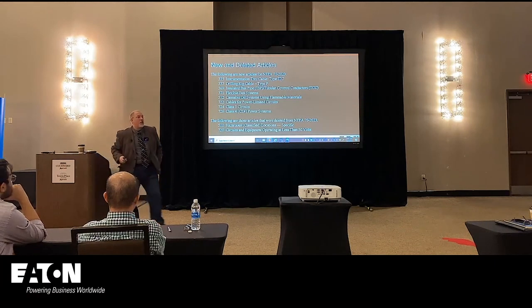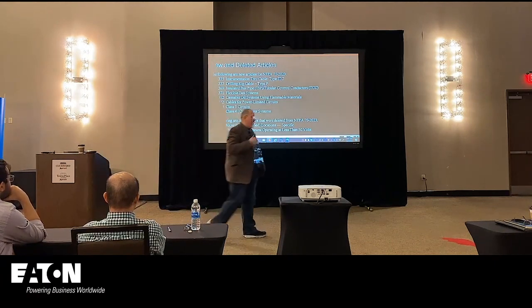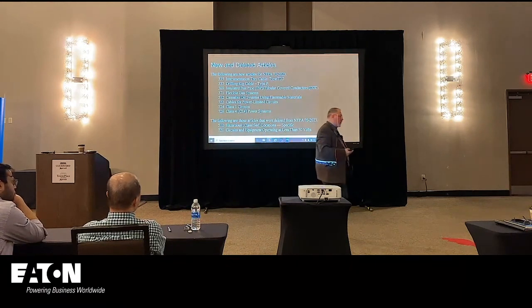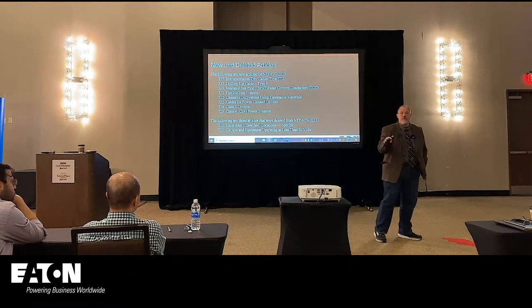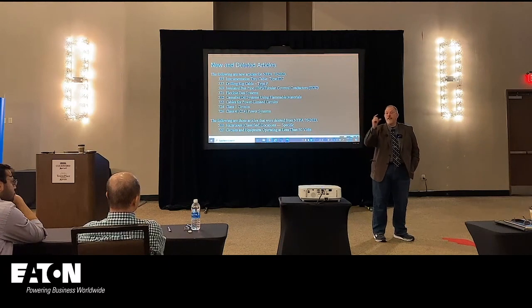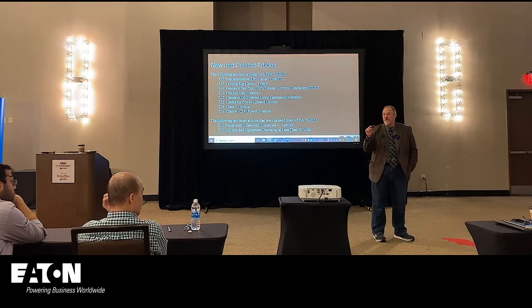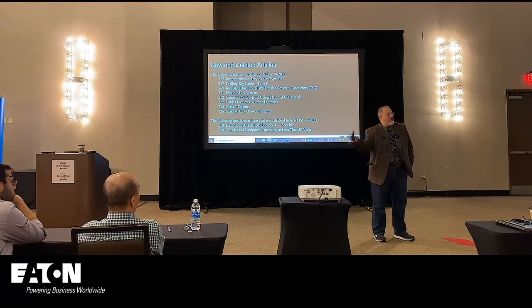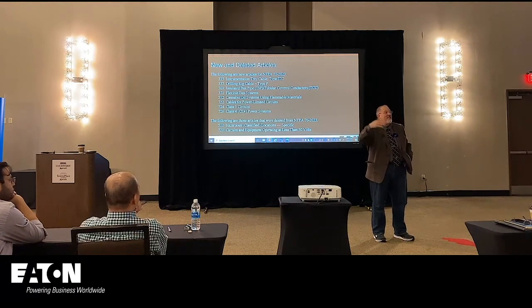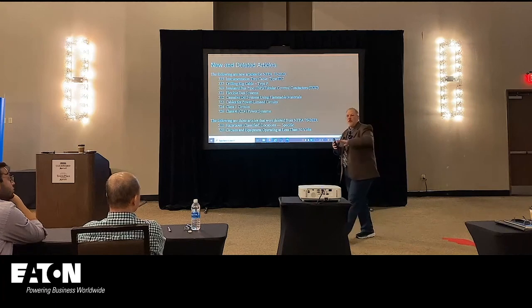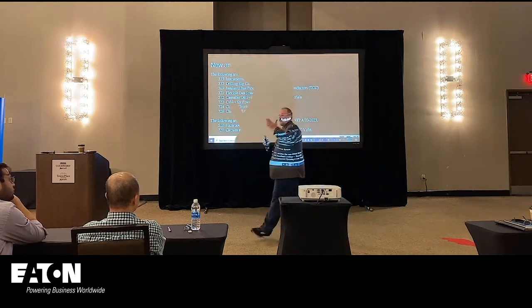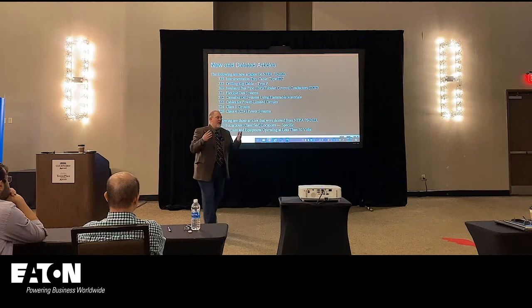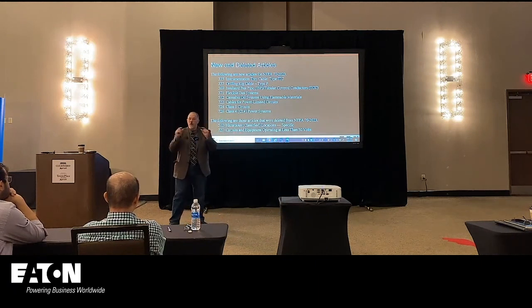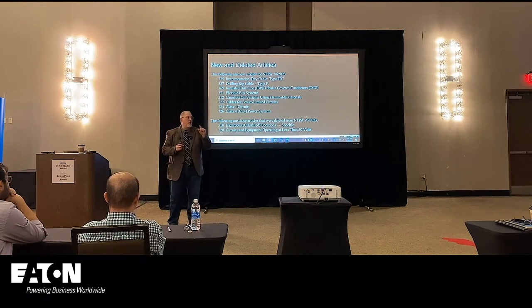Power limited in Class 4, there's a new technology on the market that drove this. There's a company out of California that is doing what they call pulsed DC power. They're trying to use more power over small conductors, right? And they want to make it a Chapter 8 wiring method, because Chapter 8 is a part of the code book, but it doesn't pull in Chapters 1 through 7. And it's not inspected typically. So they're putting a lot of power over smaller conductors through what they call pulsed DC. And they were listing it to data and communications standards.